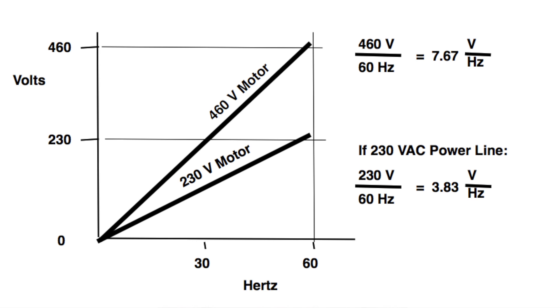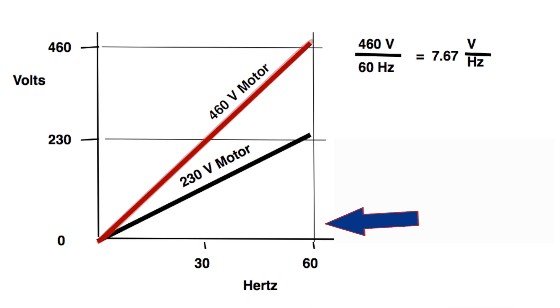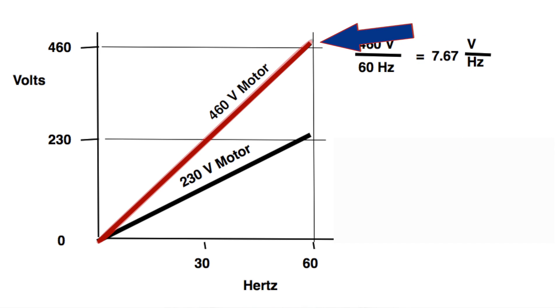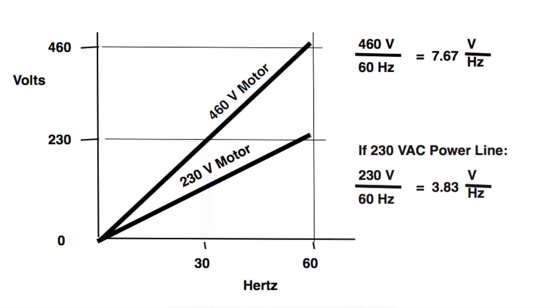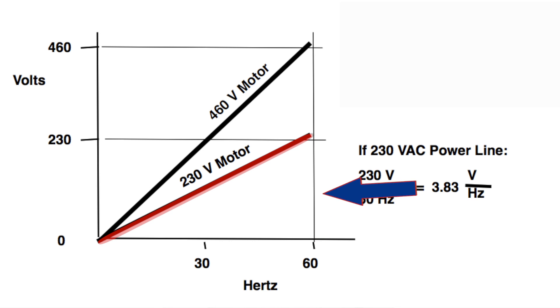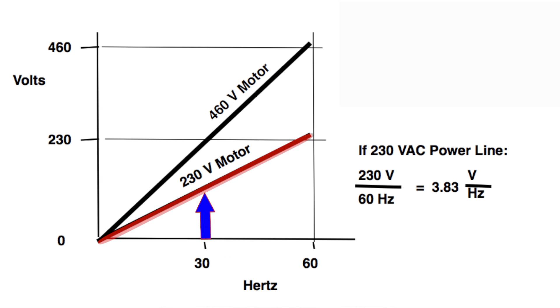To better understand flux optimization, let's step back and look at how VFDs used to operate. Previously, VFDs would output the same amount of torque regardless of the application. Notice, if we look at a 460V system at 60Hz operation, the VFD would output 460V. That same system, when operating at 30Hz, will output 230V. Likewise, a 230V system at 60Hz will output 230V, and at 30Hz, output only 115V.